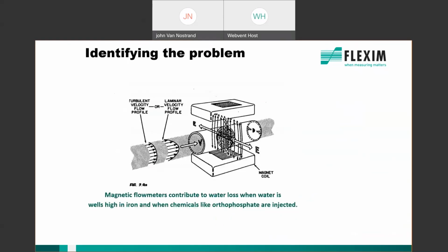The word magnetic is in the name. This coating coats the inside of a magnetic flow meter, and the relationship between the perceived accuracy and what they really are once they're installed, because of the iron content and chemicals that are injected, like to reduce the lead and copper, this accuracy is quite disparaging, and it can be as much as 50%. So that's a real concern and a major consideration for water users to think about.